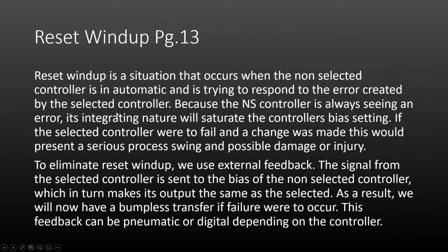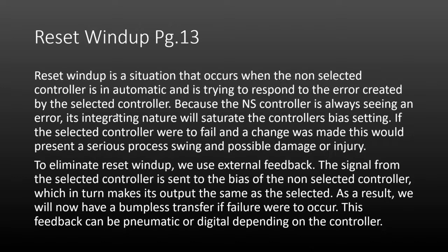Now we get into reset windup. Anytime we have multiple devices — we've seen this in cascade control — where one controller is doing a majority of the work and there's potential to switch from one device to another, we hopefully have learned the importance of making sure the unselected device knows where the selected device is in terms of control signal so that when we switch, we don't get a bump. We talked about bumpless transfer — that's the result of not being on the same page.